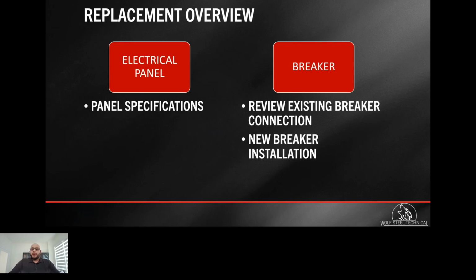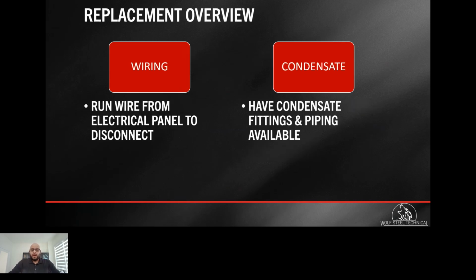Any electrical work should be done by a certified electrician, but you do want to review the breaker size, and if a new one is needed, change it out with the size that's recommended for the system. According to the electrical code, the gauge of the wire will be based on the distance and the amps of the unit. There should be proper drainage for the inside coil and the outside unit. Since the outside unit will have ice developing underneath it, we don't want to cause any hazards on any walkways.